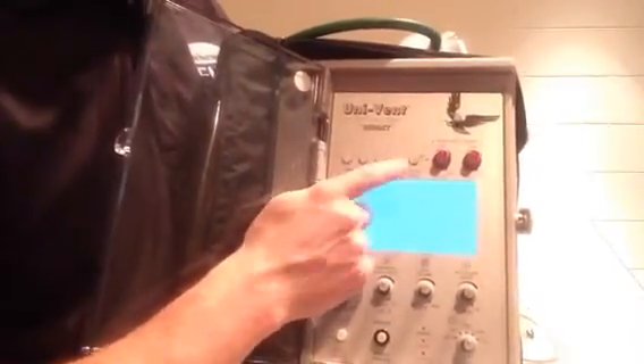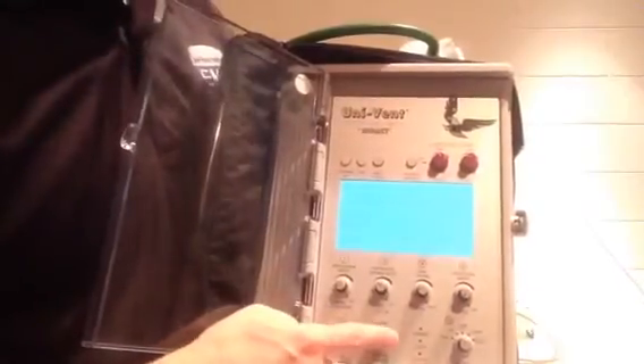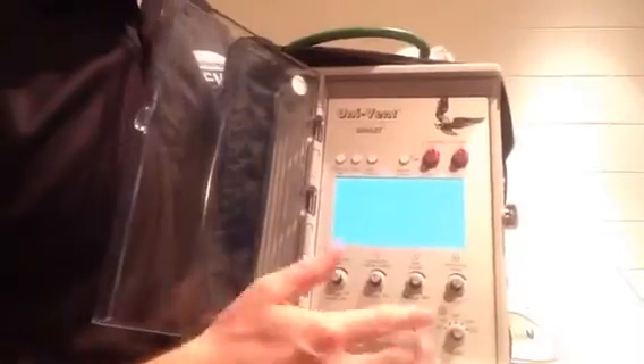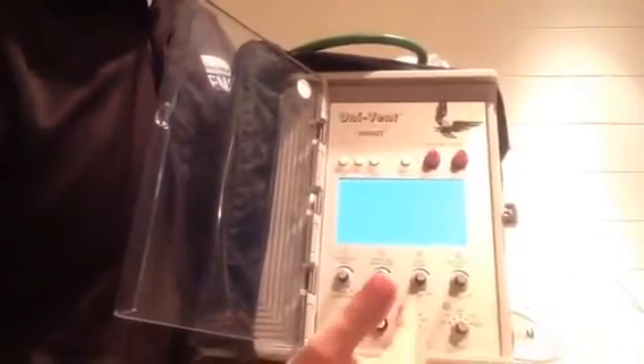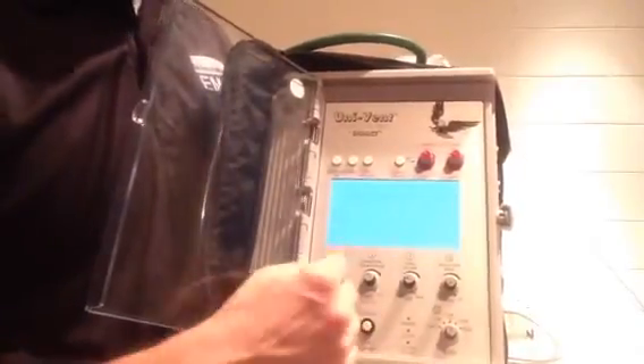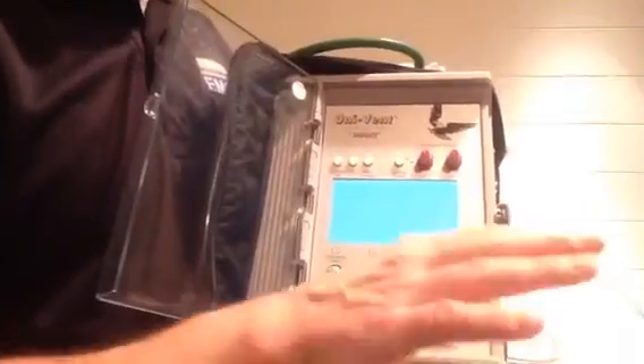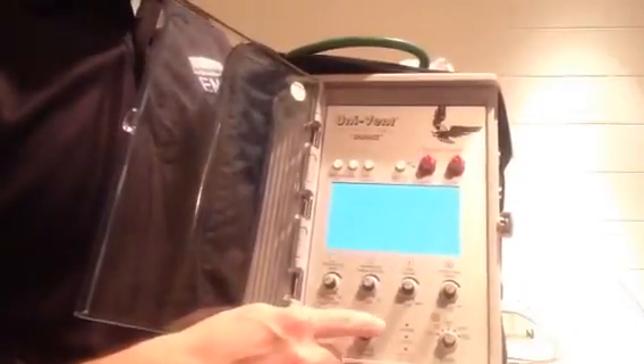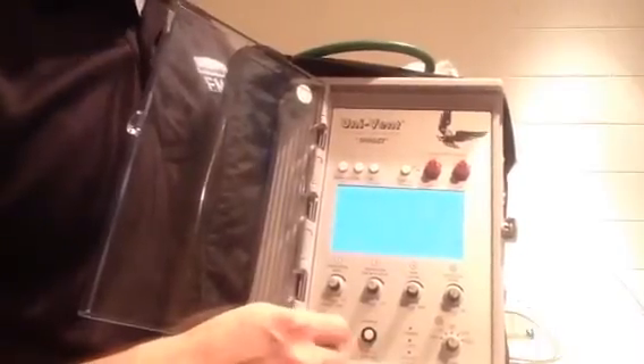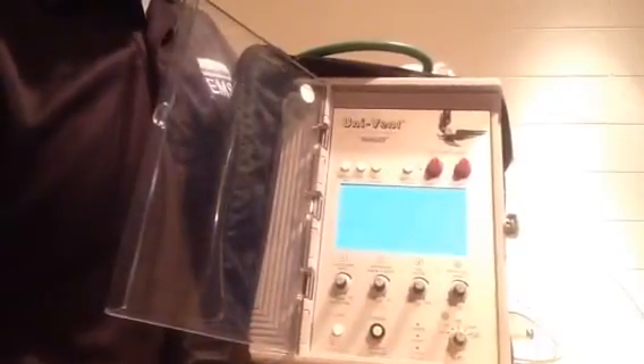The other aspect we have is we have external air, a sigh, and PEEP. You also have a manual breath trigger down here. So if you're reconfirming your tube placement, or you move the patient, anytime we do a patient movement, the tube should always be checked. So here is your, if it's very low breath, low volume, and very slow, then we need an actual breath. So we can breathe, and then check the other side, and we can go ahead and take a breath. Just be careful of air stacking. You don't want to end up having barotrauma.